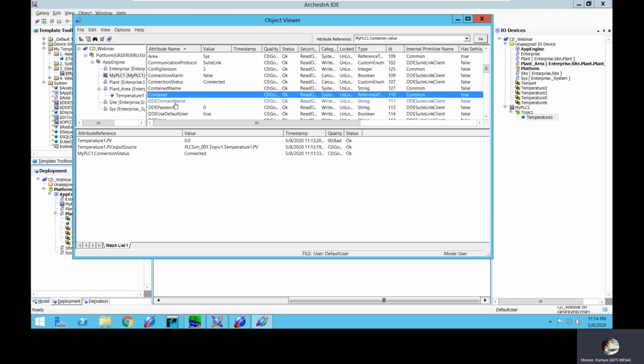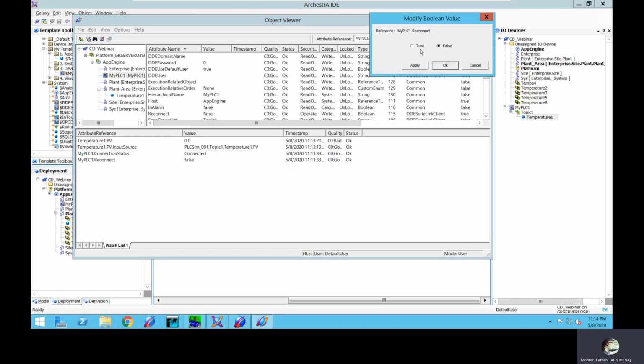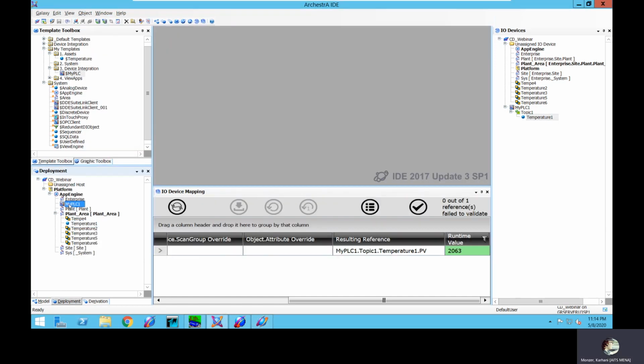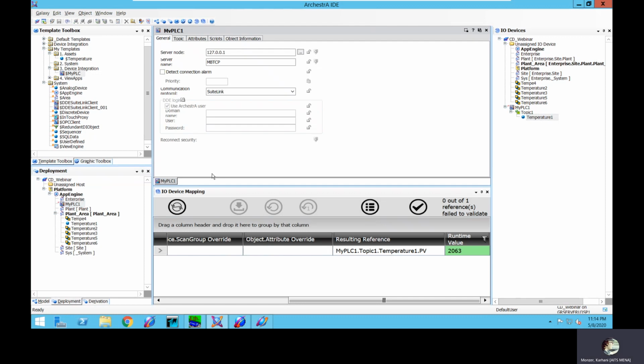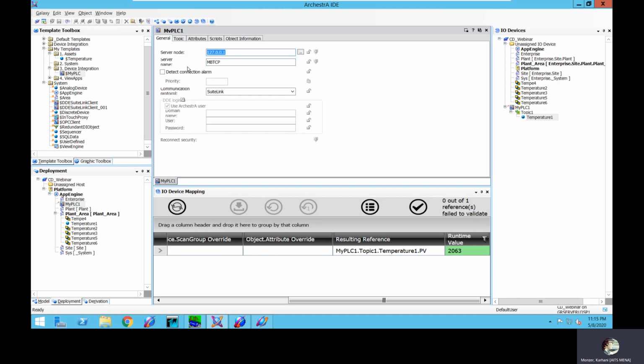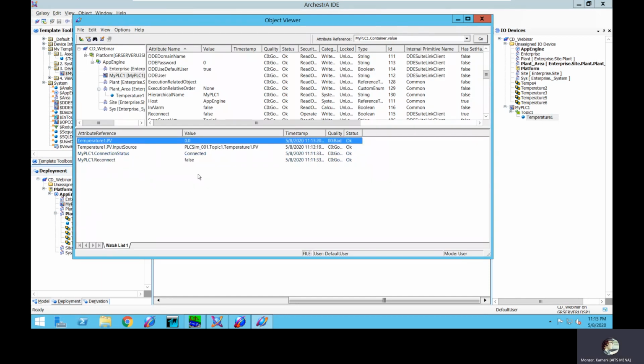If it's not connected, search for something called reconnect. And by the way, you can reconnect and give this order automatically from a script. We'll not cover it today. However, if it's disconnected, double click, try to reconnect it. If it's still not reconnected, please open the device integration server and check those three values, which must match your communication driver. Once it's connected, still bad.